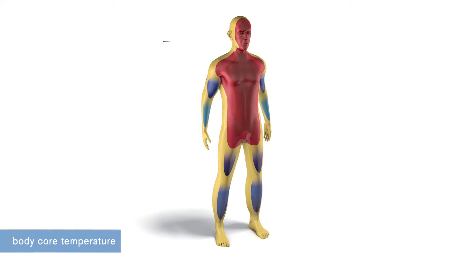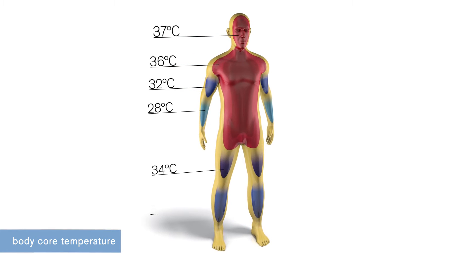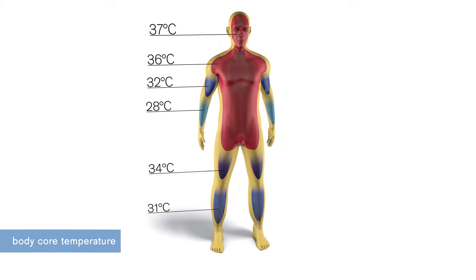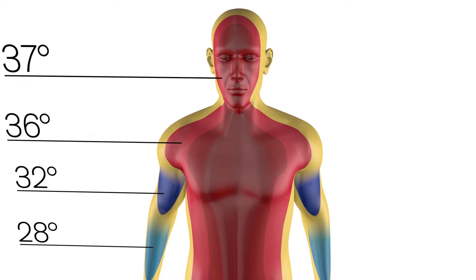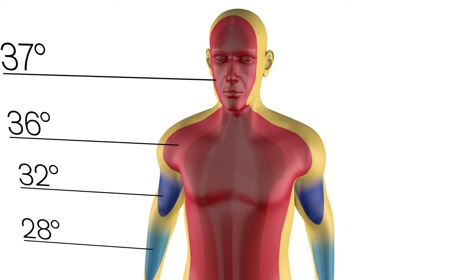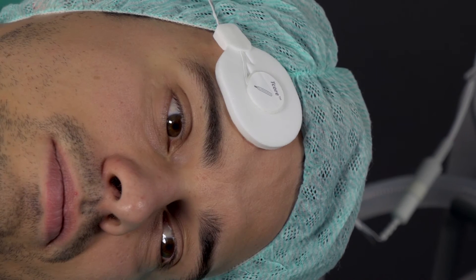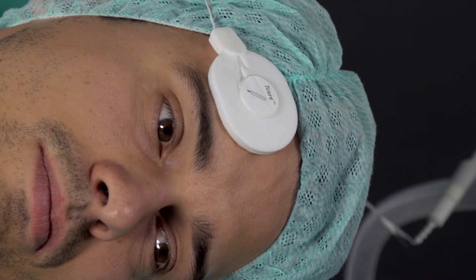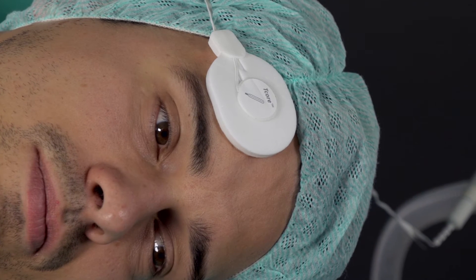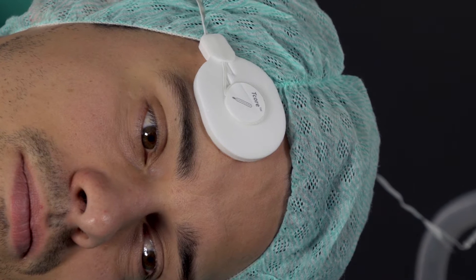Nowadays, the continuous monitoring of the body core temperature is an important measure for early detection of hypothermia. Previously this was accomplished primarily with invasive procedures involving the oesophagus or bladder, because only these procedures guarantee a high degree of accuracy. But now, Dräger has developed a body core temperature sensor applied to the forehead of the patient that delivers the same accuracy when measuring body core temperature as invasive procedures.